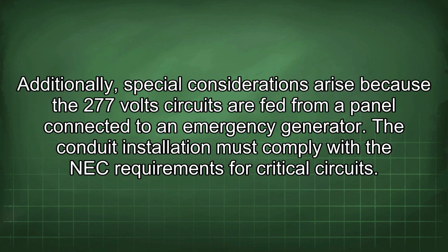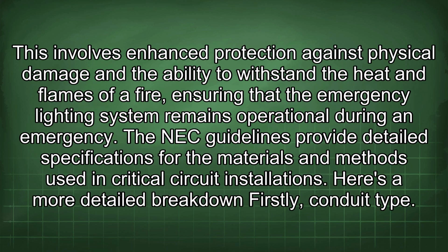Additionally, special considerations arise because the 277 volt circuits are fed from a panel connected to an emergency generator. The conduit installation must comply with the NEC requirements for critical circuits. This involves enhanced protection against physical damage and the ability to withstand the heat and flames of a fire, ensuring that the emergency lighting system remains operational during an emergency. The NEC guidelines provide detailed specifications for the materials and methods used in critical circuit installations.